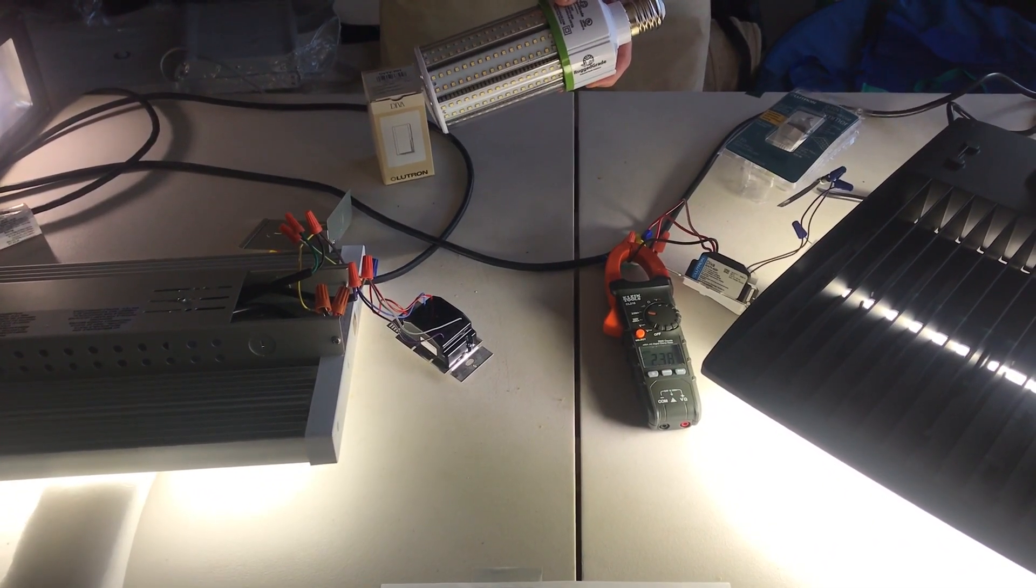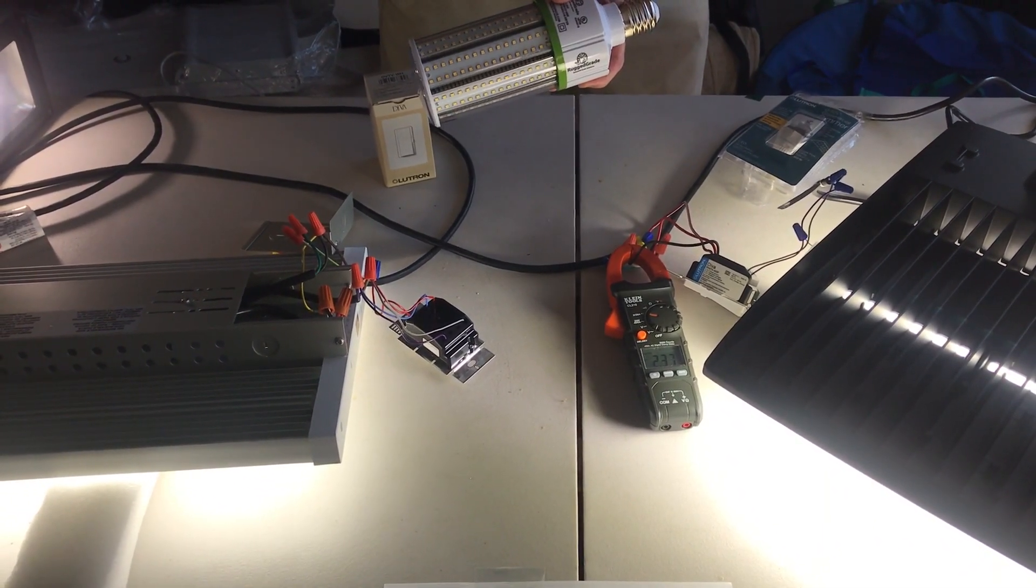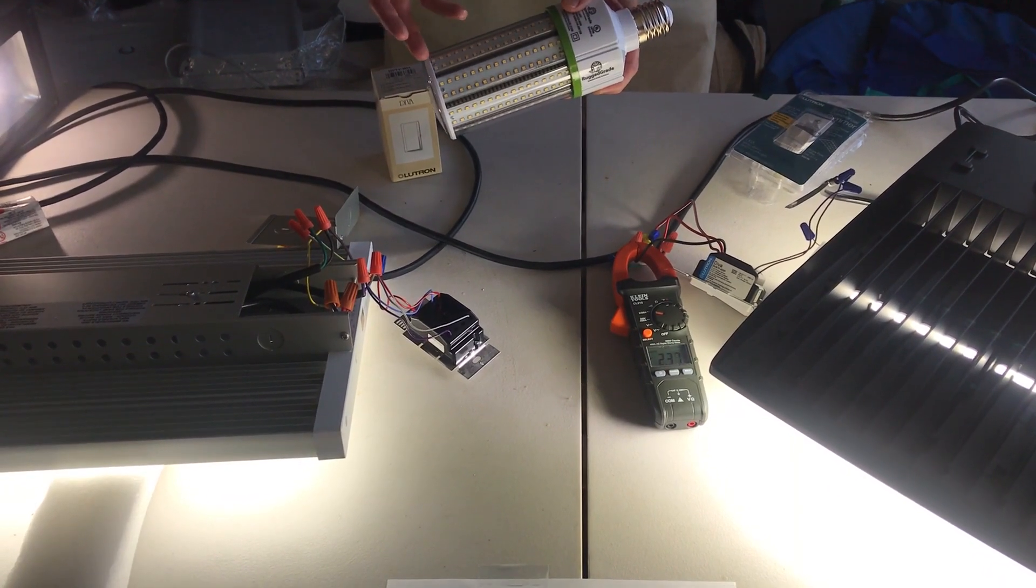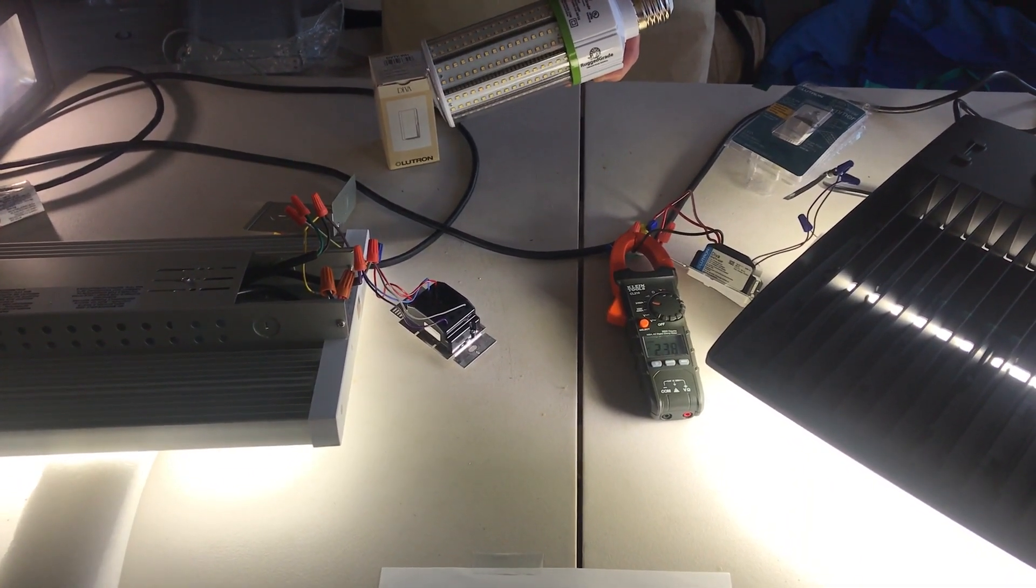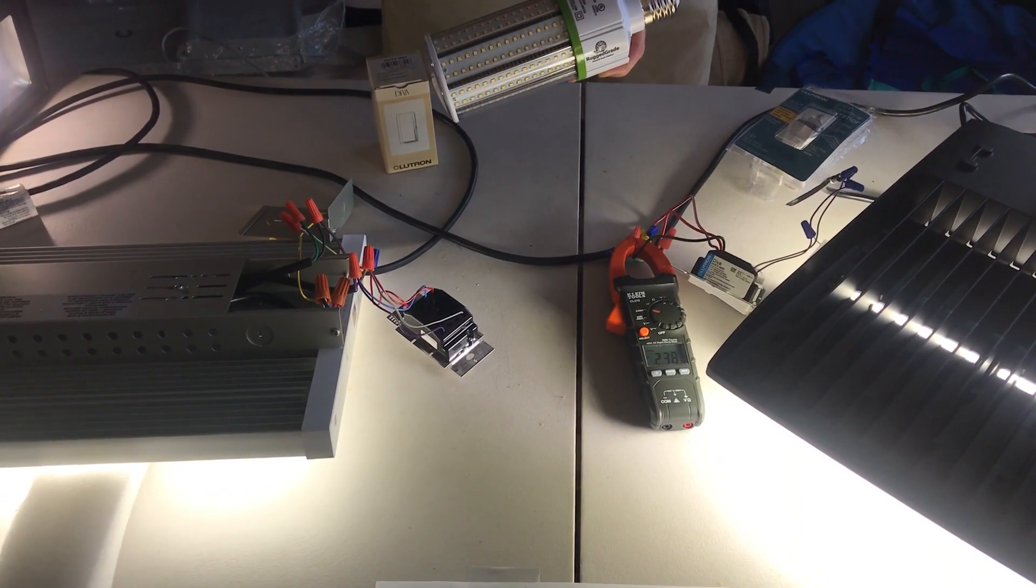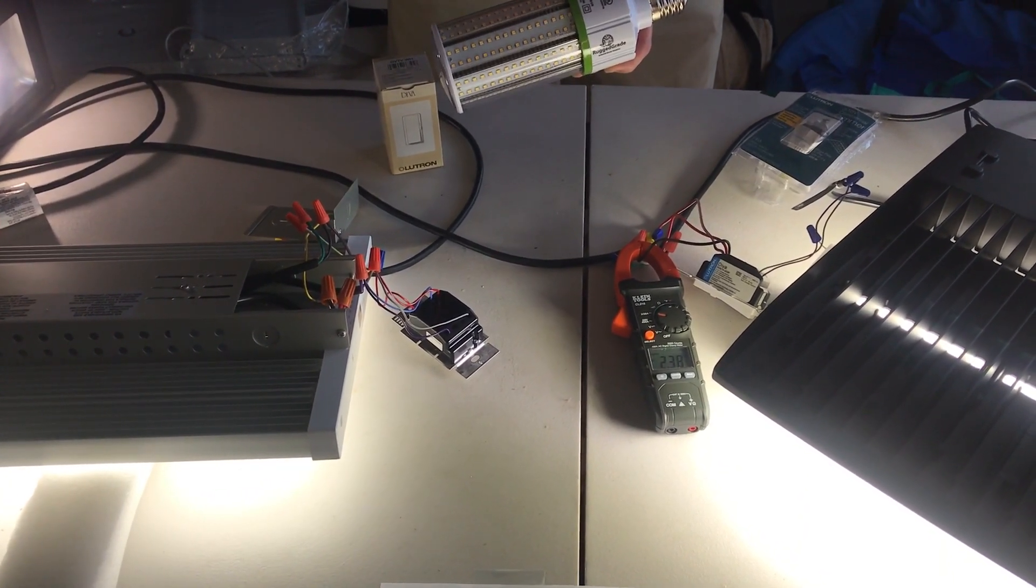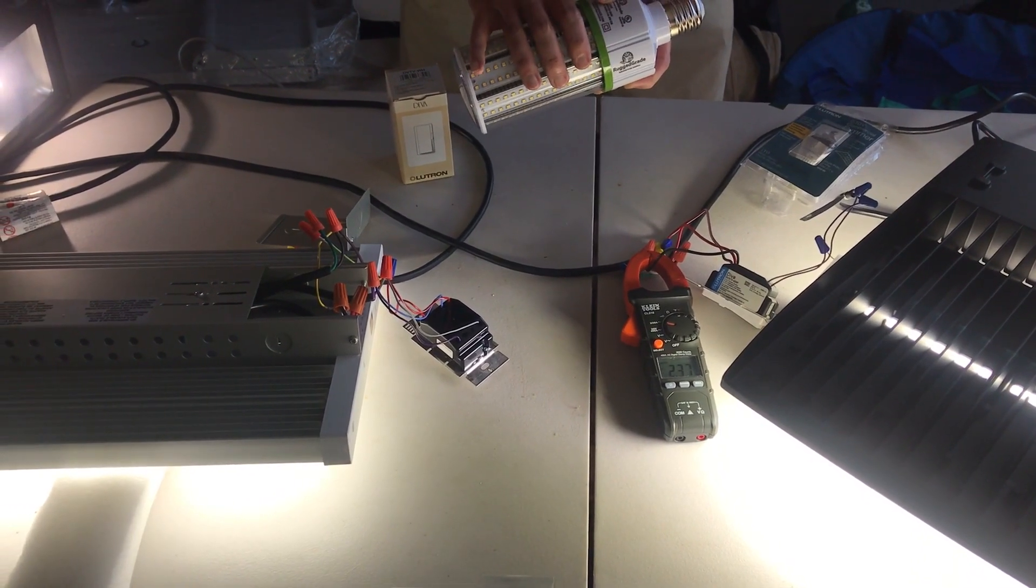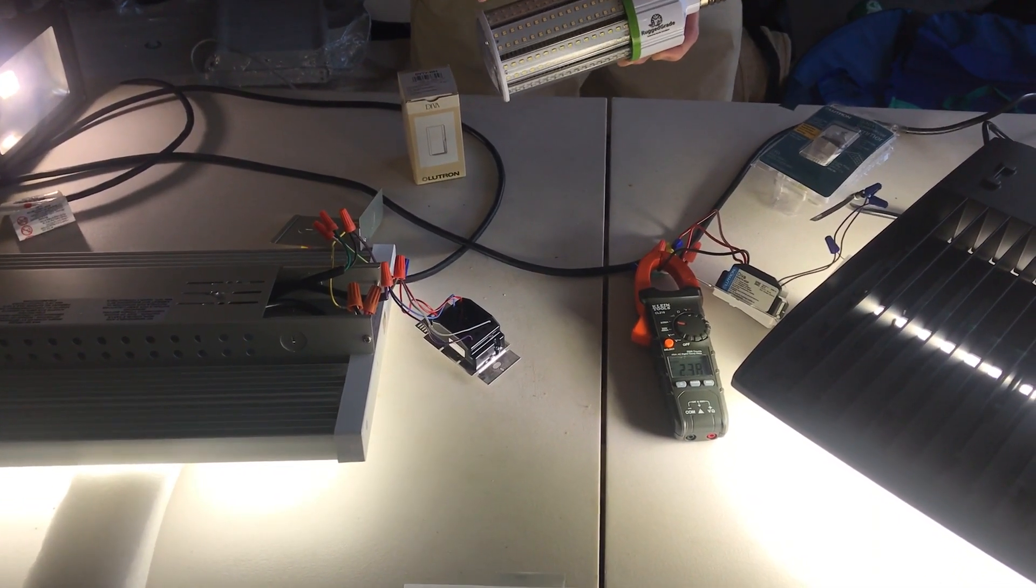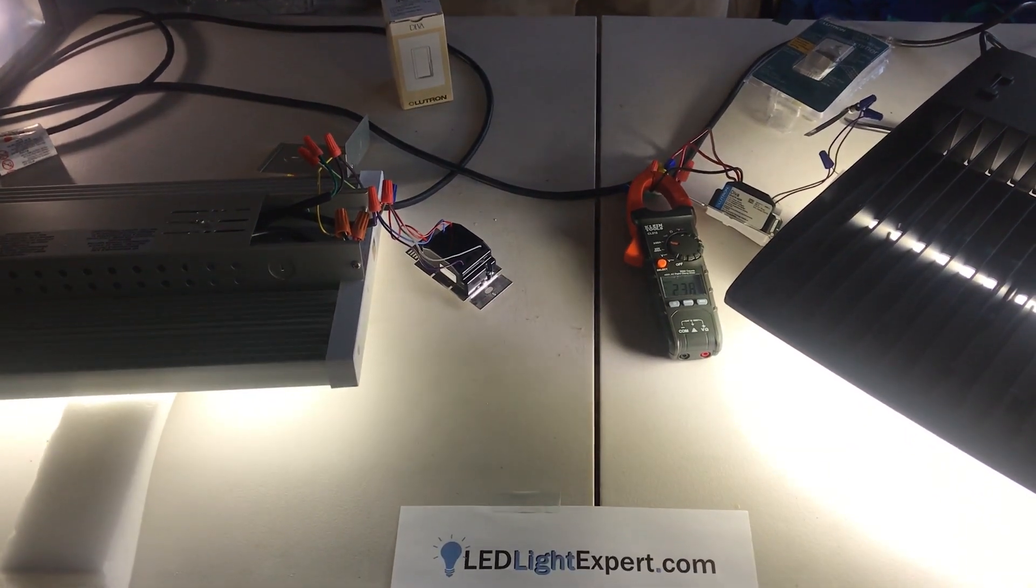Any sort of watt restriction or power restriction on that is going to cause these to flicker and hum. You've probably all had cheap LEDs that do that. As you go from full output, it only gets worse. There is no such thing as dimmable high output bulbs. We have to switch to dimmable fixtures and use the 0 to 10 volt dimming to do that.